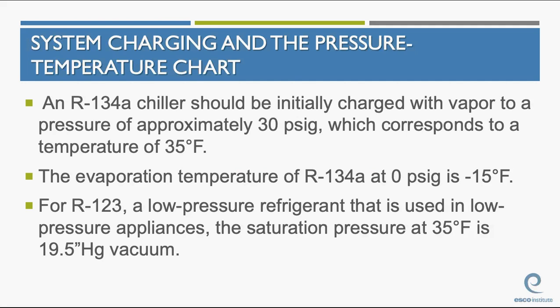A 134A chiller should be charged with a vapor to approximately 30 psi, which corresponds to a temperature of 35 degrees. That's because at 0 psi, the evaporation temperature of 134A is negative 15 degrees. And if you get any questions on this, all you have to do is remember, we do not want to freeze water. So look at your temperature pressure chart and find out where the water freezing point is. And the pressure you're looking for is going to be the one that's slightly above that.